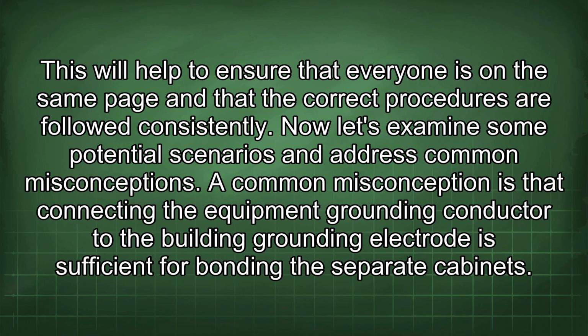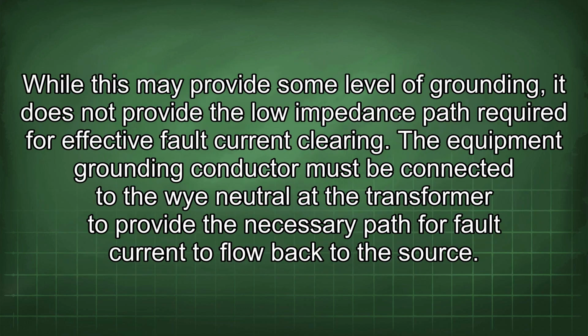Now let's examine some potential scenarios and address common misconceptions. A common misconception is that connecting the equipment grounding conductor to the building grounding electrode is sufficient for bonding the separate cabinets. While this may provide some level of grounding, it does not provide the low impedance path required for effective fault current clearing. The equipment grounding conductor must be connected to the Y neutral at the transformer to provide the necessary path for fault current to flow back to the source.